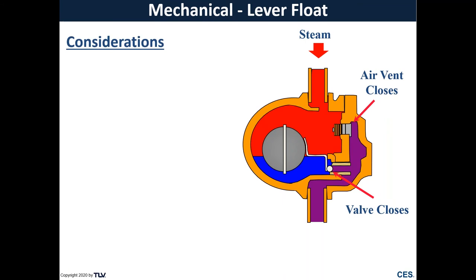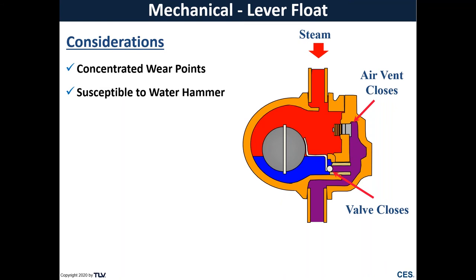Some considerations for the steam trap. You still have similar linkages, a single seating surface being a single valve head and a single valve seat, which could eventually wear out, giving you leaks. And there's no added measure of protection against water hammer. And so if you get into a water hammer event, it could damage your lever mechanism or even damage your seating surfaces. And this trap is going to be sensitive to how it's installed because of the float and lever mechanism.